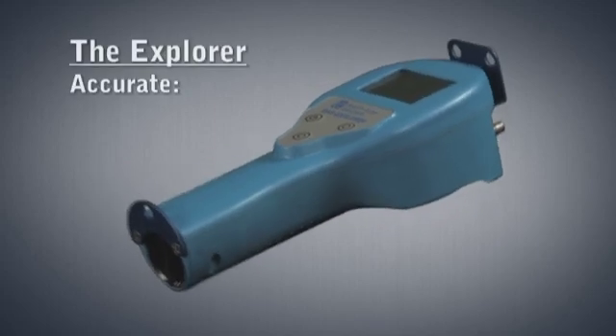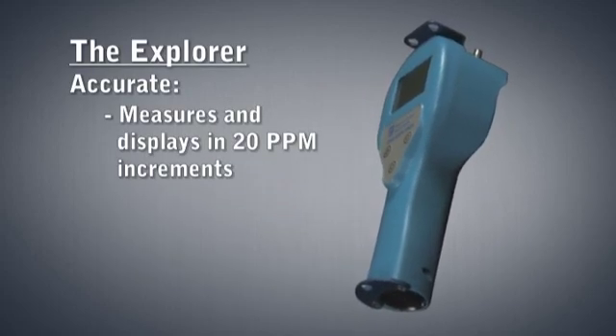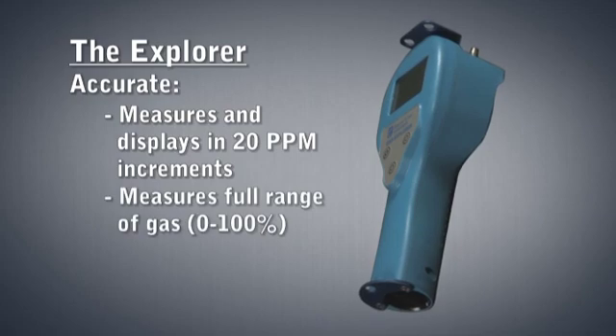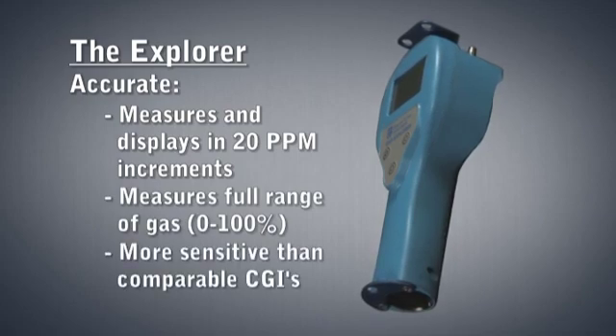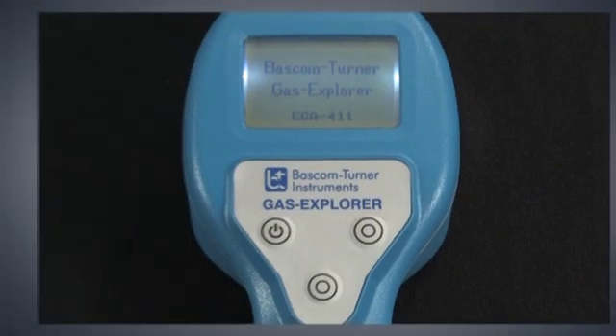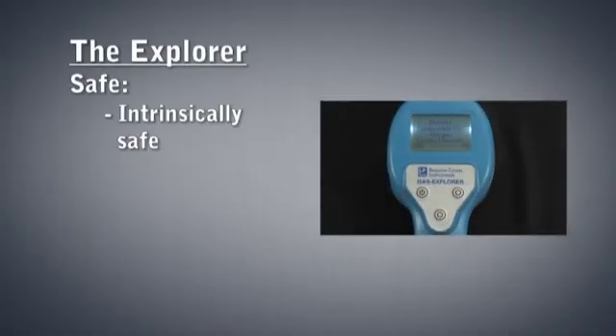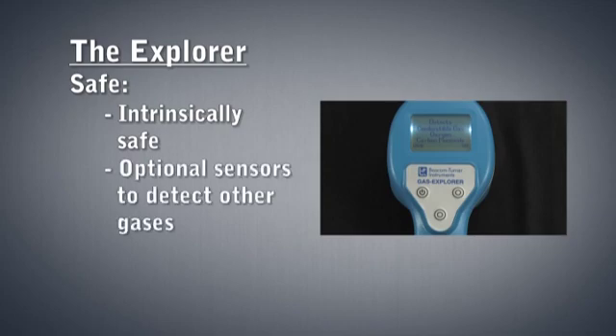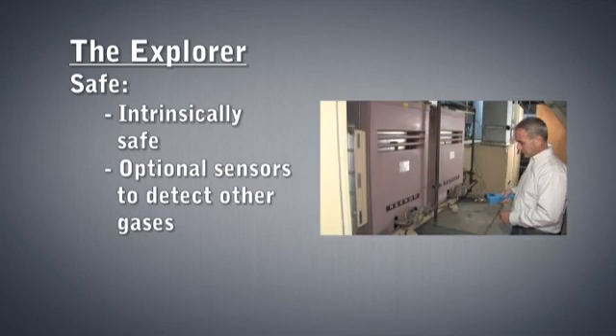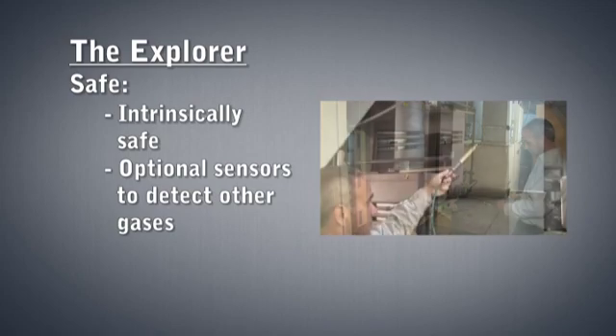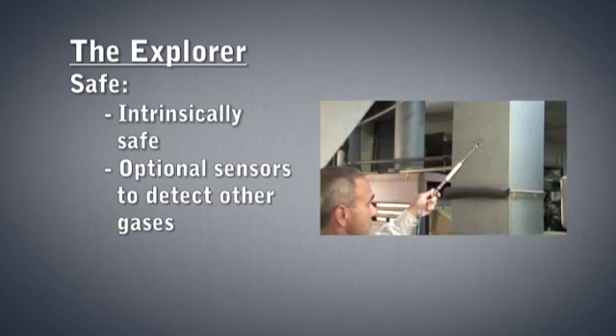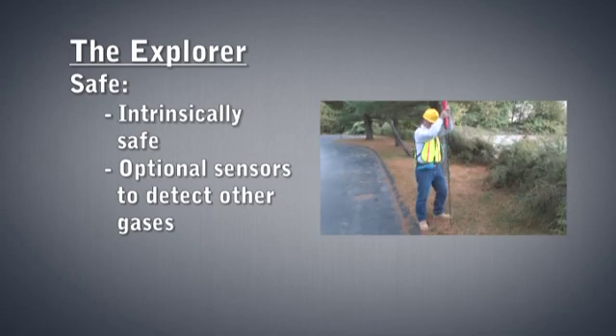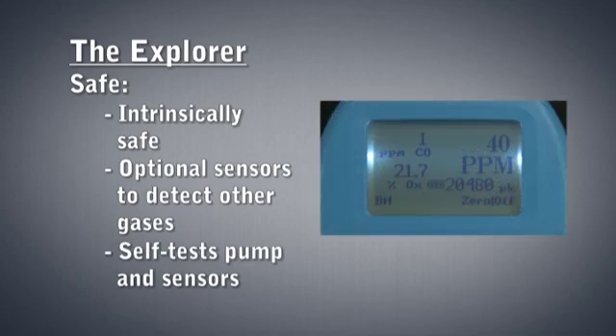The Gas Explorer measures natural gas from 20 parts per million to 100% gas. The Explorer can be used indoors and outdoors and has 3 modes: monitor, track gas, and bar hole. The Explorer is intrinsically safe. Optional sensors to detect other gases make it suitable for safe entry, which further enhances its versatility and value. An intrinsically safe pump automatically samples ambient air, flue gas, or bar hole gas. The Explorer also self-tests its pump, sensors, and battery on a regular basis.